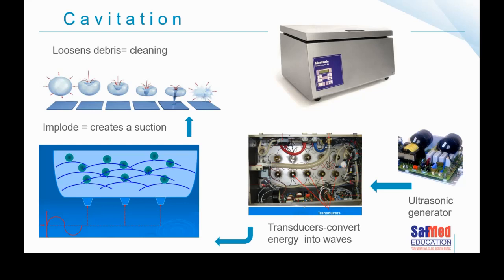Ultrasonic baths run at different hertzes. Not all machines have the same hertz. Some instructions for use will specify that an item needs to be cleaned in an ultrasonic cleaner at a specific hertz. So please don't just throw any old instrument into the ultrasonic cleaner. It's very important to consult the manufacturer's instructions for use to know whether a particular device can or can't go into an ultrasonic cleaner. Some items, some tiny laparoscopic items, may have their screws loosened too much and therefore shouldn't go in the ultrasonic cleaner. Other items are really well suited for going into an ultrasonic cleaner.